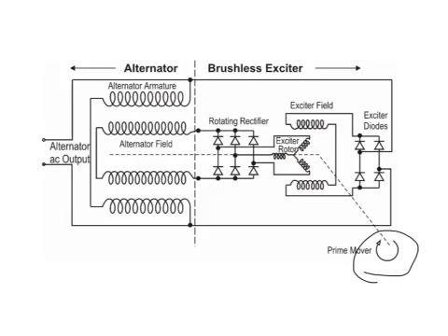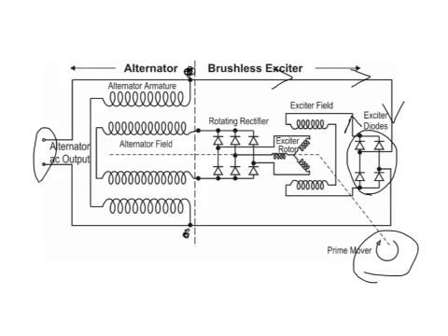At this point we have no load attached at the alternator output — nothing is connected. We're going to look at where current flows once this thing starts turning. The prime mover brings the rotor up to rated speed. With no load attached, there's only one place for current to flow: to the brushless exciter. Current starts to flow as AC current, because we're connected across the same two points all the way to the alternator output. That AC current enters a full-wave bridge rectifier, which converts AC to DC, and that rectified DC current now flows out to the exciter field.